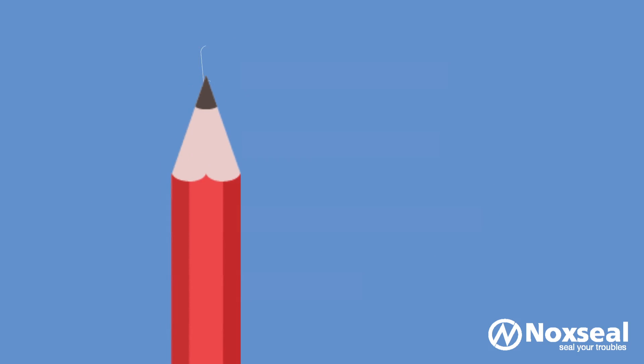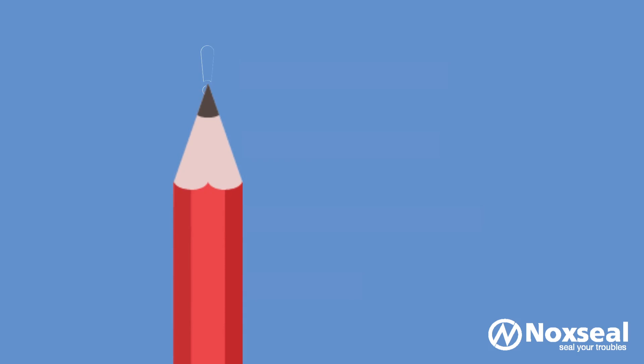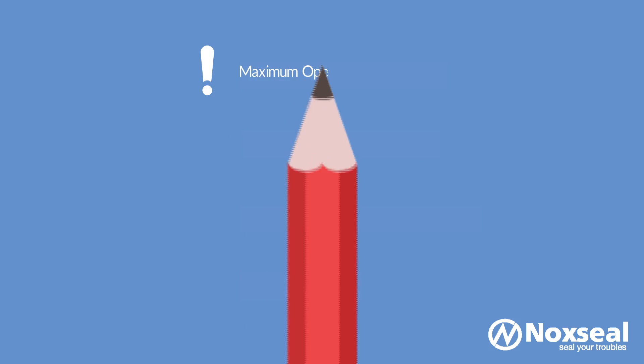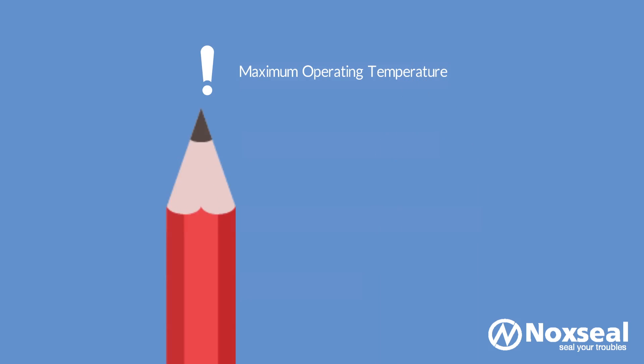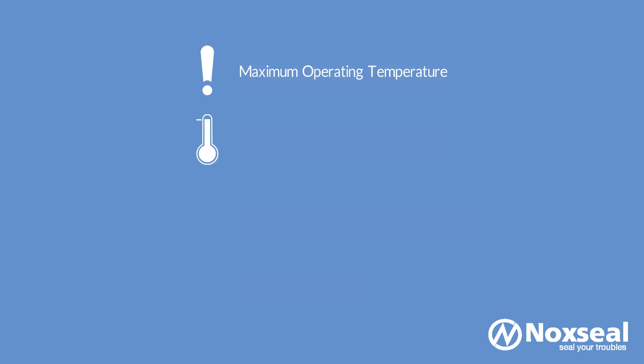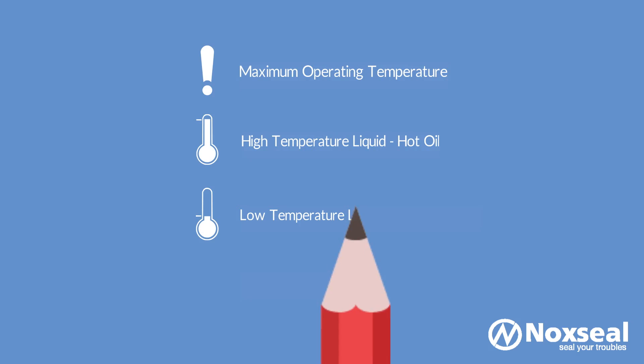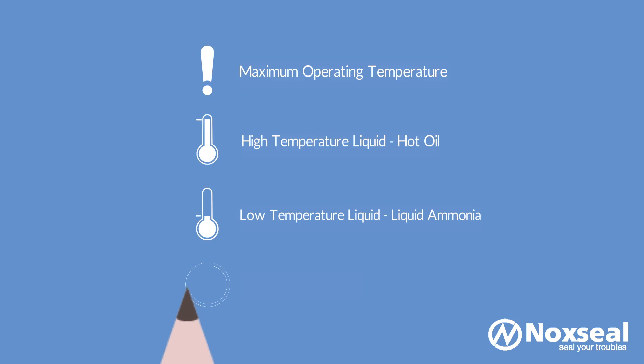Step 5: Temperature. Temperature plays a major role because different seal materials are suited to handle different temperatures. It is vital to know a seal's maximum operating temperature because all seal materials have an upper temperature operating limit that should never be exceeded. While some pumps handle liquids at high temperature, others handle low temperature liquids. The seal material and mating surfaces used in pump mechanical seals must be selected based on the liquid temperature, and they should be able to sustain the temperature of the fluid.